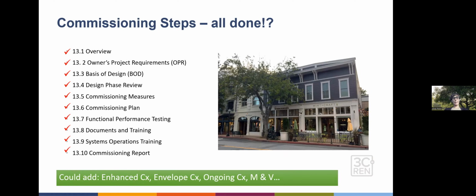There could be enhanced commissioning, where your commissioning authority reviews submittals and comes back 10 months after construction is complete, during occupancy but within that warranty period, to check all the systems again, do an occupant survey, and check for any gaps. There's also ongoing commissioning, checking seasonally whether everything is performing well, with measurement and verification.